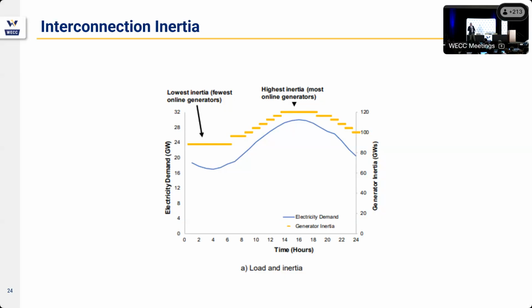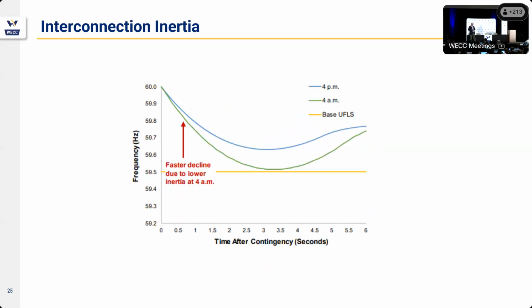IBRs have changed that. So here's a frequency curve for the same resource loss with different inertias. Basically what it used to look like, at 4 a.m. we would drop much lower, to under frequency load shedding, than we would at 4 p.m. And that was strictly a function of the inertia on the system, which gave governors time to act. It gives the prime mover connected to the rest of the interconnection generators time to open, time to inject more energy, and to recover the balance of generation to load. And time was what we really got out of inertia.